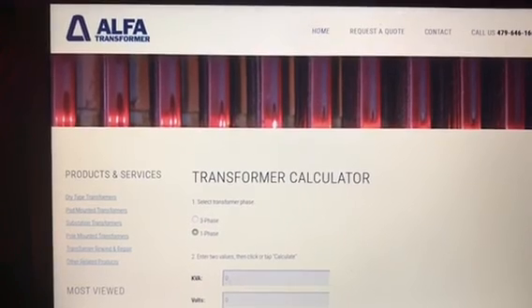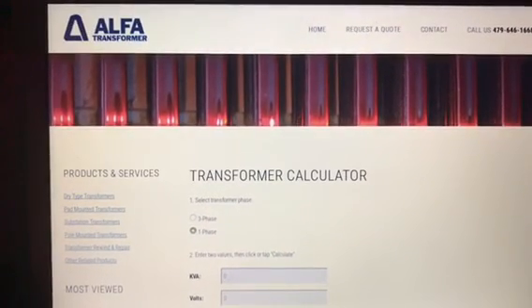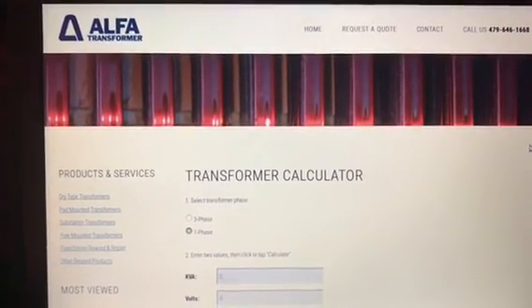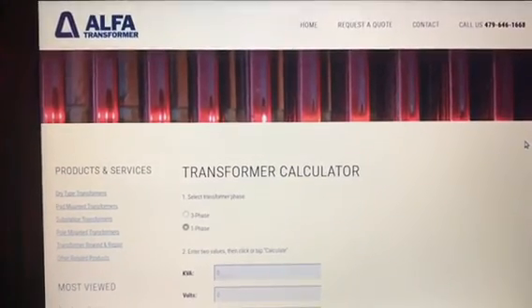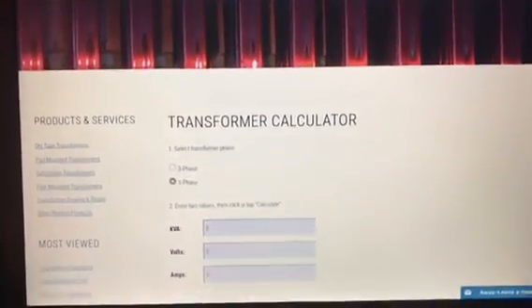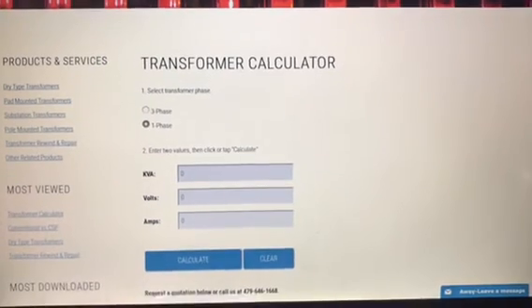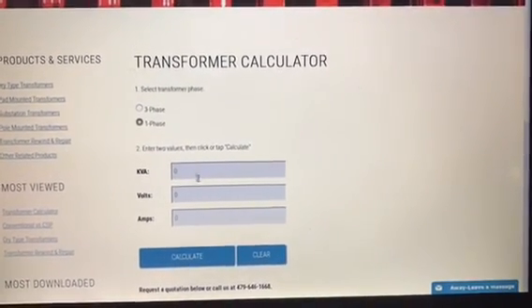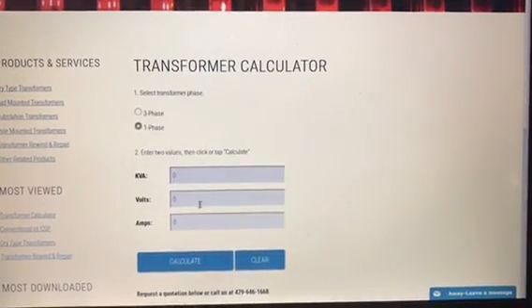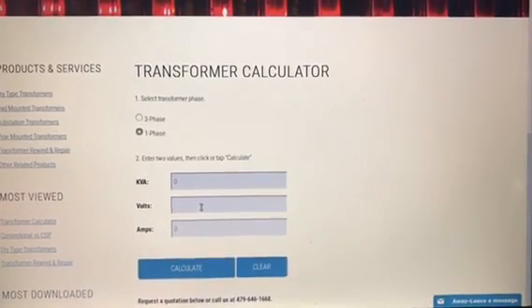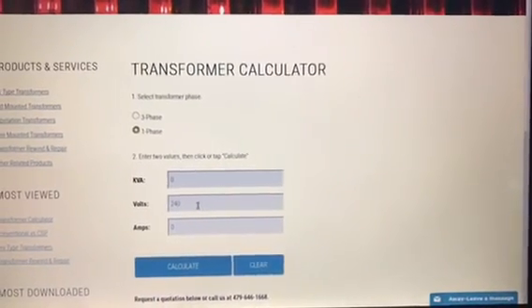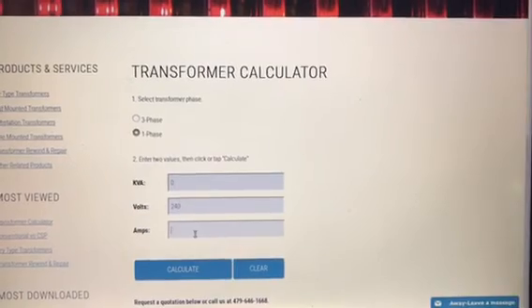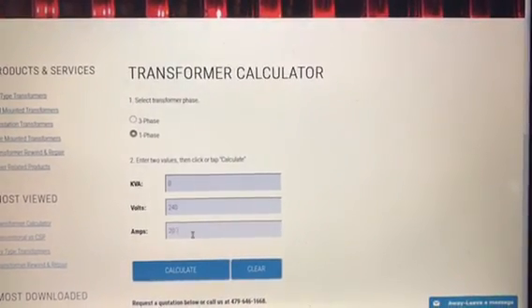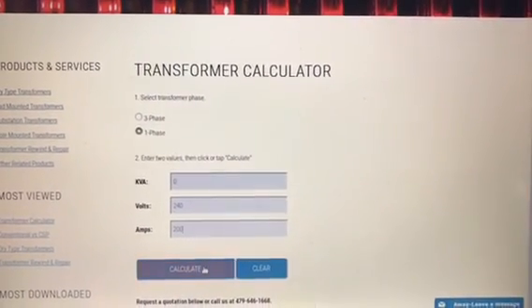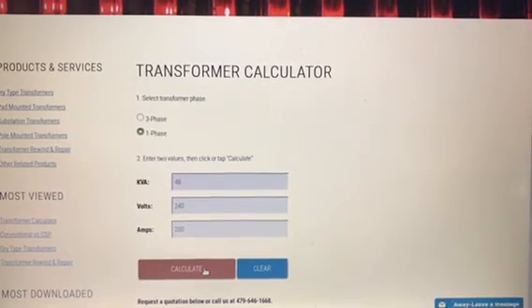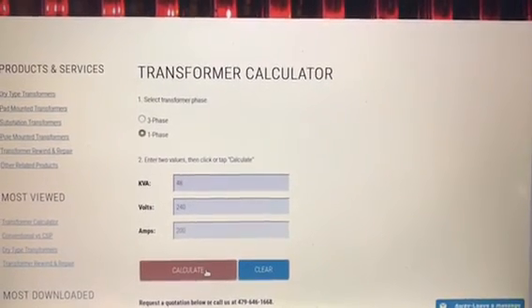This is a transformer calculator from Alfa Transformer. They actually make some power line transformers and some stuff for regular light commercial duty. But what I'm going to show you here is, if you have a 240 volt service, and this is from the manufacturer, and you're going to have 200 amps continuous on that service, then you should have a 48 kVA transformer.